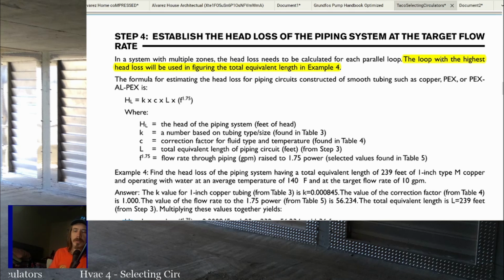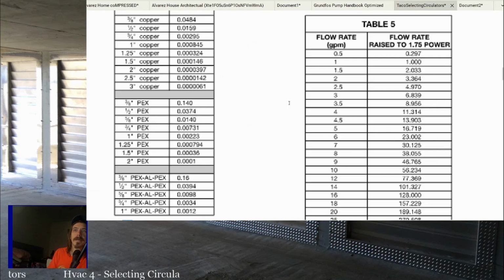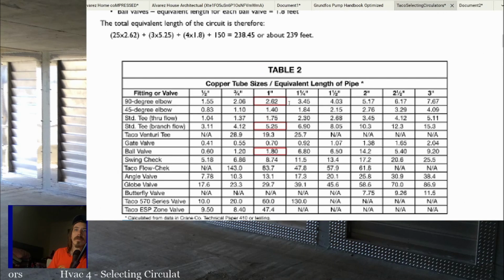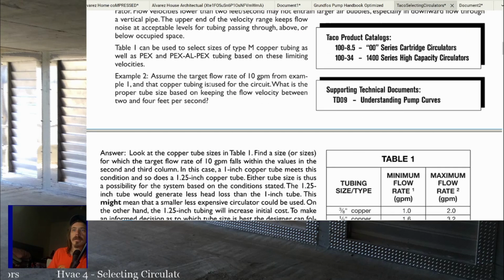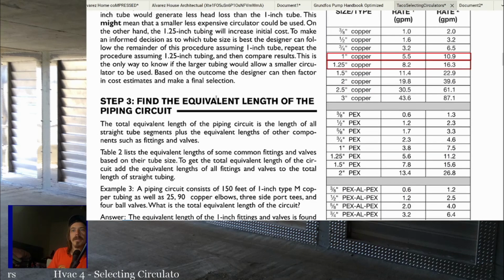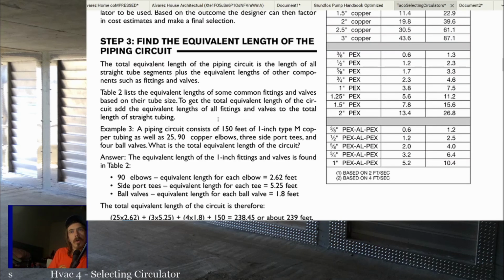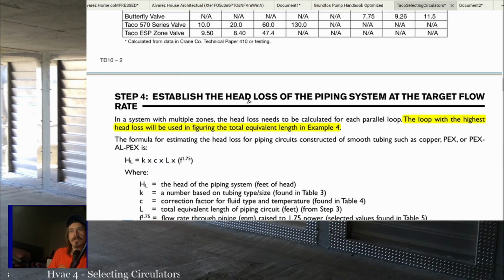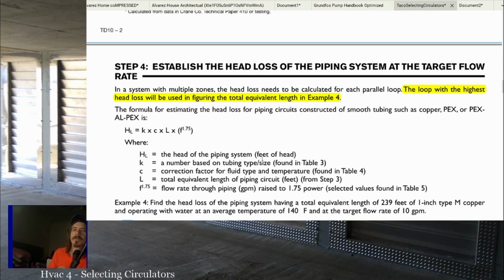Like I said, this is a good primer on looking ahead to how we design other things. The formulas are a little different because we're dealing with water as a fluid instead of air. Our pressures are going to be different, which affects how these things are calculated, but everything is pretty much the same. So far we've gone over knowing how much flow we want, figuring out how big our pipe's going to be, mainly so we can figure out the equivalent length, the longest run. Then we establish what pressure we have to work against based off our longest run. The formula for estimating head loss for piping circuits constructed of smooth tubing such as copper or PEX is this.